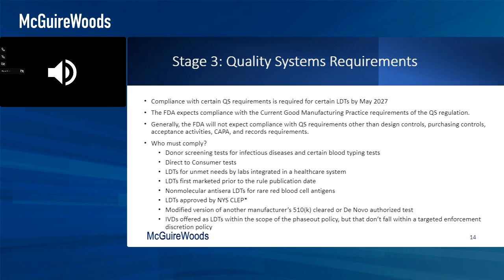And it's not necessarily super directly addressed in the guidance, but when you're dealing with LDTs and IVDs that rely a lot on technology now, where you've got some AI built in, you've got some training built in, when you're changing your algorithm for how you're determining results, you've really got to make sure that you're tracking those design changes. It's the same thing with, as you change your test, if you've got a test that's on the market currently, and you're good, if you make any change to that test, you're going to have to go through this process. FDA has basically indicated that they are going to consider that a new test, and you need to walk through these processes.